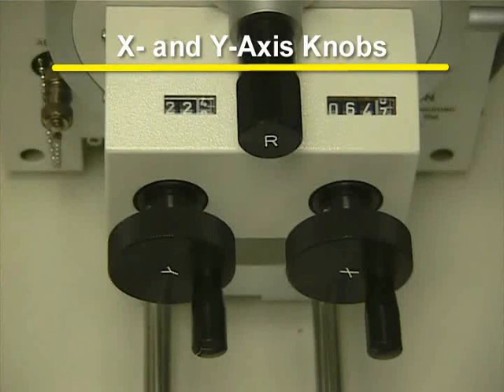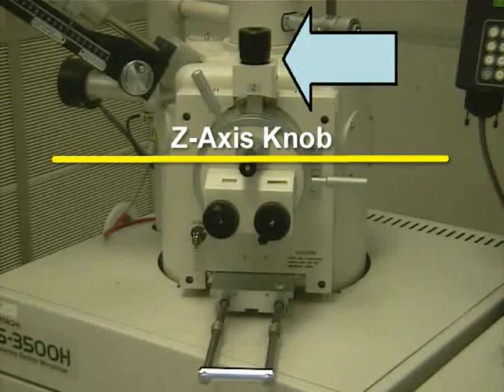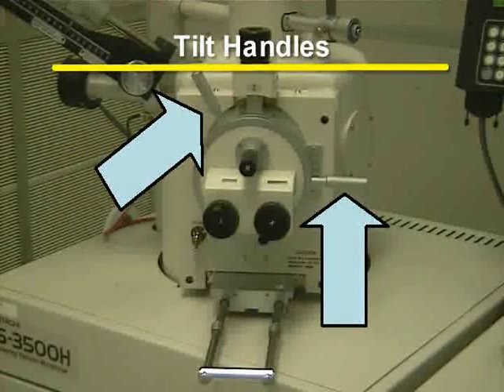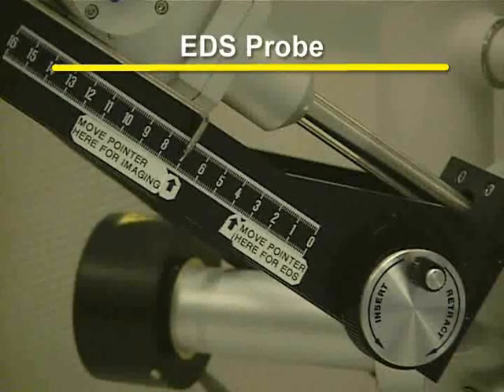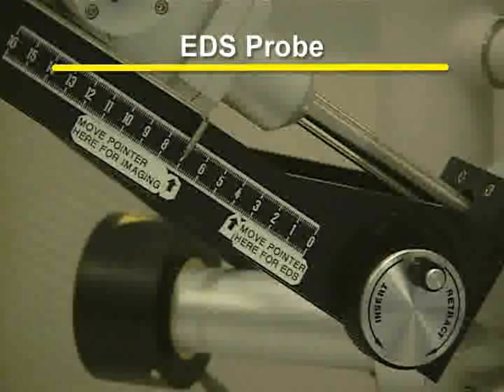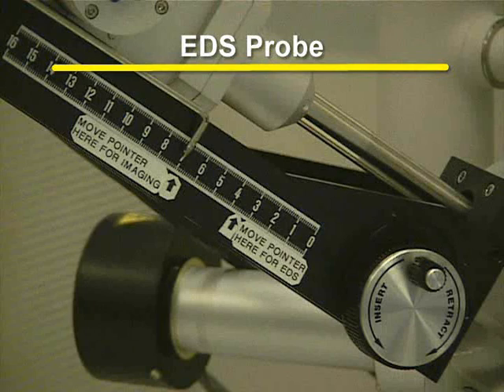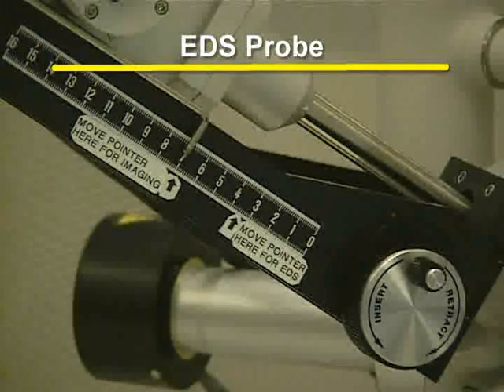The X and Y knobs are used to move the stage from left to right and from forward to back. The Z-axis moves the stage up and down. The tilt handle rotates the stage from 0 to 60 degrees. Be careful when tilting large samples. It is possible to crash the sample into the lens. The EDS probe selector is located above the chamber. It is used to set the mode of the EDS probe. For our training video, the EDS probe will be set to imaging.